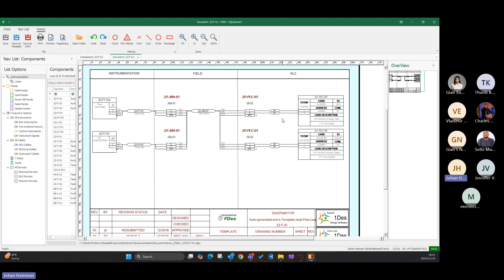I don't have to draw lines, and I will show you a bit later in this presentation how you can start from scratch and get to this very quickly. But here is the tag from the P&ID itself. It tells me this is the instrument. The description is my analog input plus-minus. There's my instrument cable, white, black, screen, and there's my field section, which is my junction box, its terminals, a multi-pair cable going to the PLC information, to a landing strip, single wires to a PLC analog input card, analog output card.